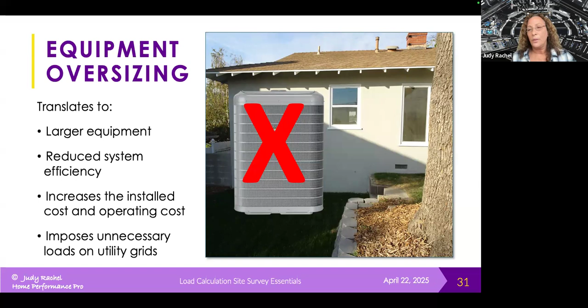When we oversize equipment, we also have to make our ducts larger, or we need to add more duct runs, which also means more grills. So we're inflating the installation cost when we do that. In this house with an oversized system, the person who designed this thinks that they need 3 grills in this area to condition this area, as well as air, heat, cooling going to all of these bathrooms, this water closet, just all of these rooms.